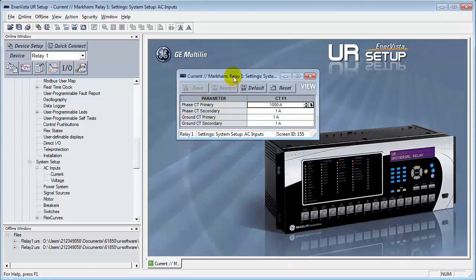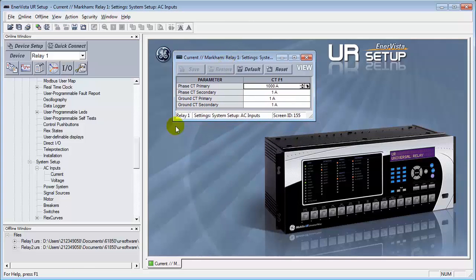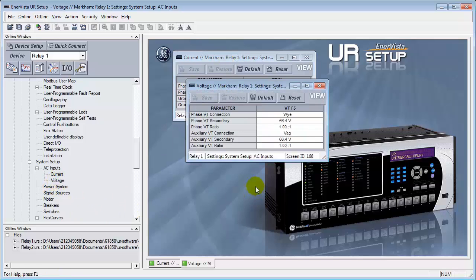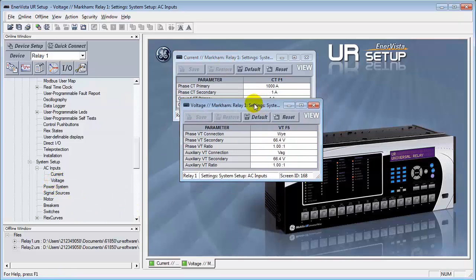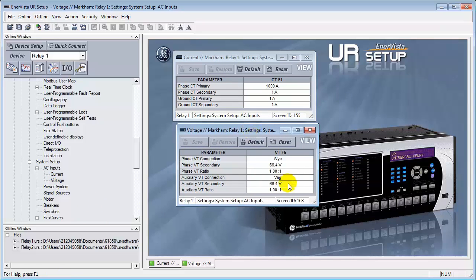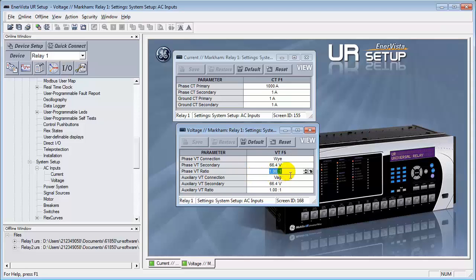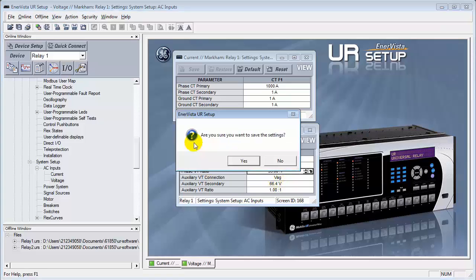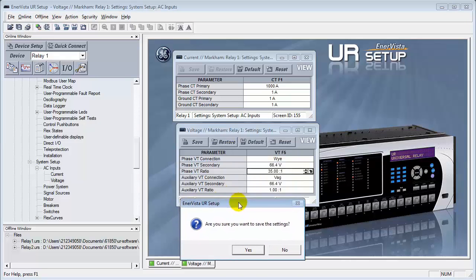Next, we'll configure the voltage inputs, where we have a choice of either Y or Delta. Let's leave it for Y for this present configuration. And the only thing we'll change here is the phase VT ratio from 1 to 35 to 1. Press the Tab key. This will allow us to enable the Save. We'll save this.